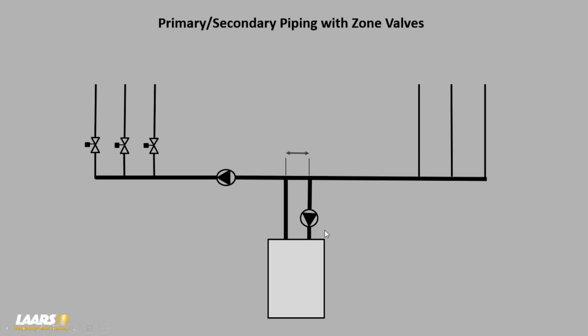So I'm going to refer to this as our primary. Here's our secondary. The boiler pump, keep in mind, on our FT is right inside the cabinet, so you don't have to add this to the system. However, you will need a system pump if you're doing zone valves, or zone pumping, you'll need your zone pumps.